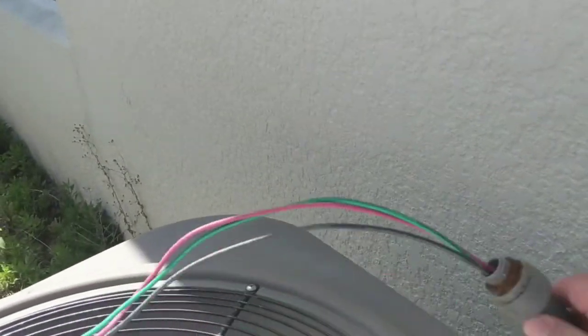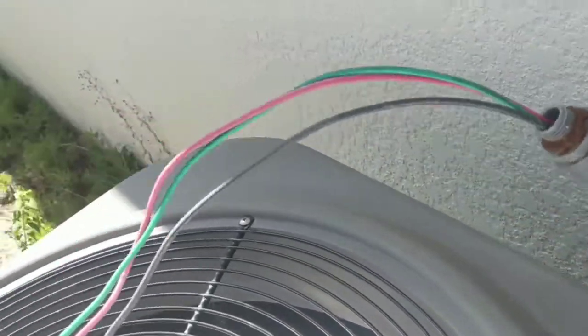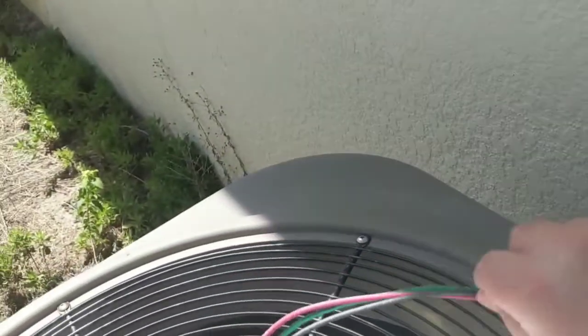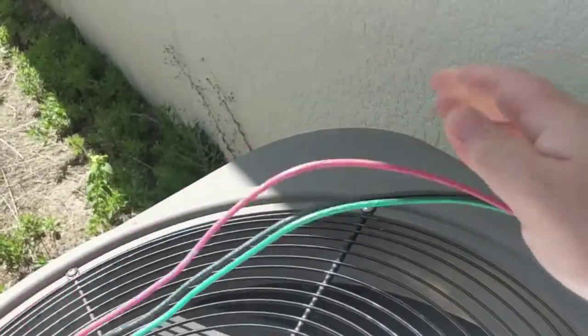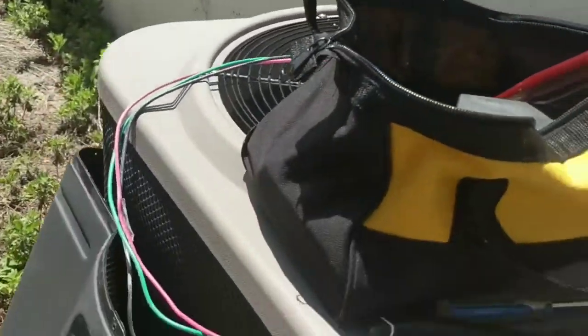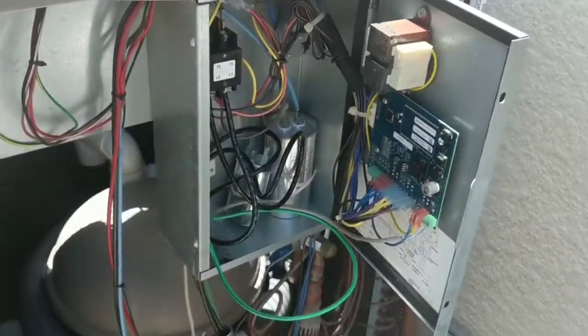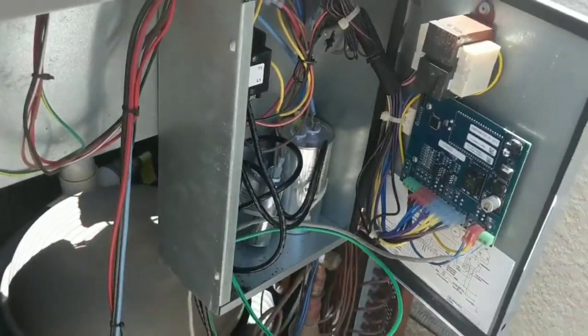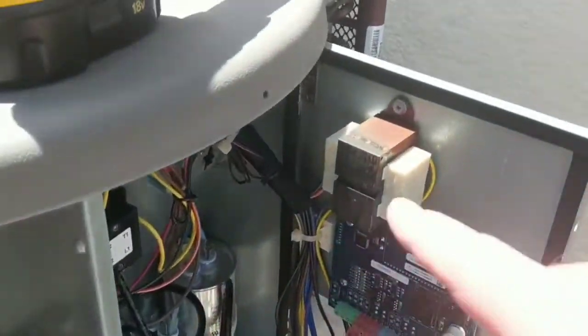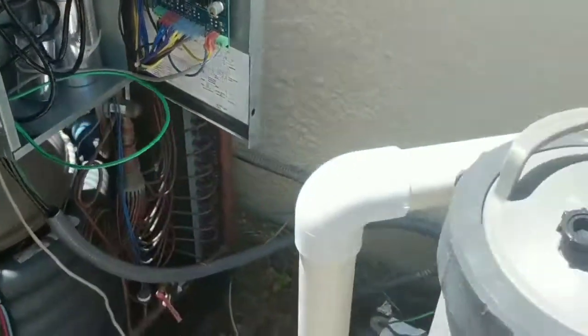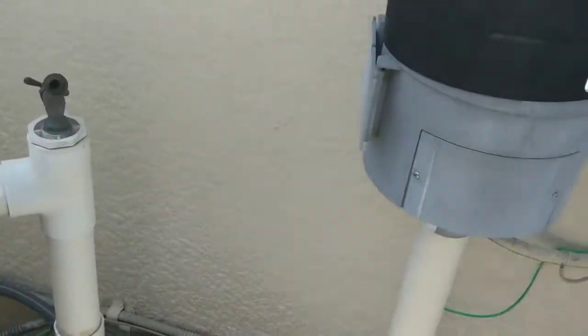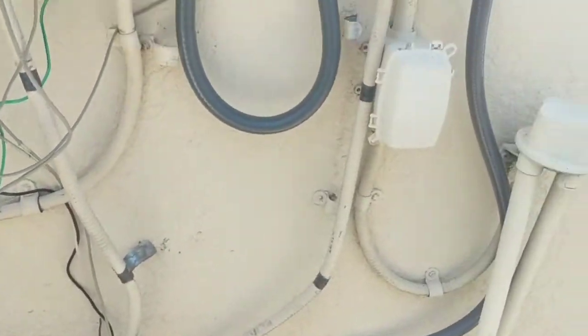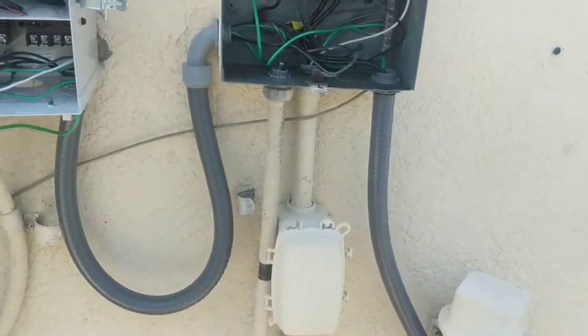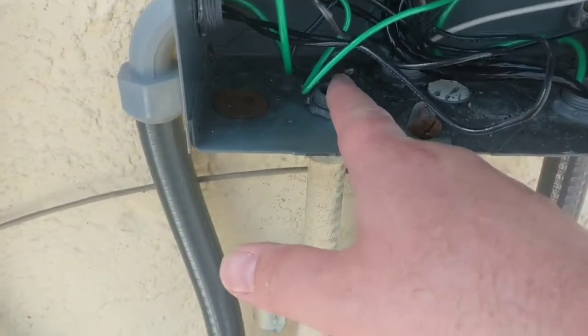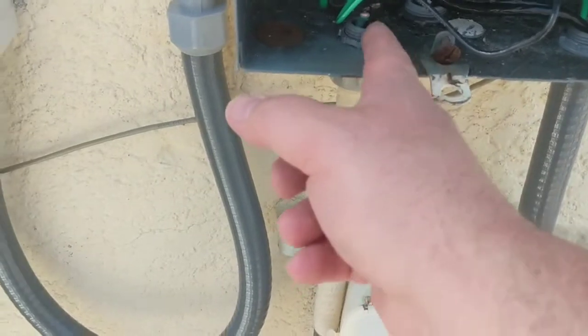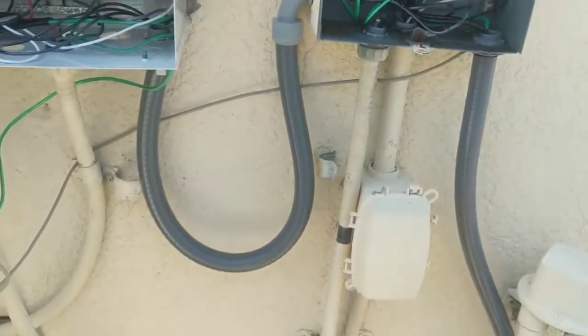This is what I cut off that the guy who installed this heater put on here — way too small a wire for this thing. A 240, 60 amp setup is rated at 4 gauge, 6 gauge at the very least. You can see the transformer is all black, and the wires I pulled out were melted to the sleeves. The conduit was melted, everything was melted — here's the old 6 gauge sticking out, and it was all just melted and fried.